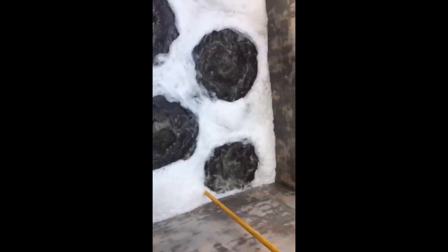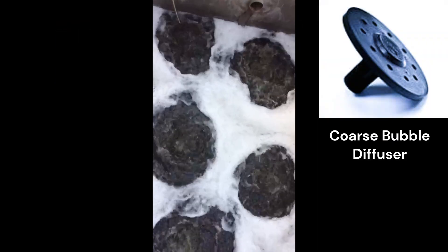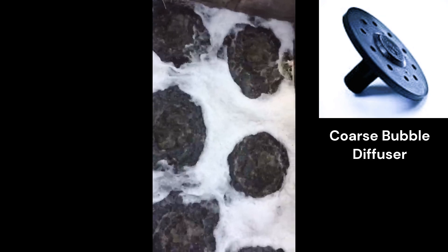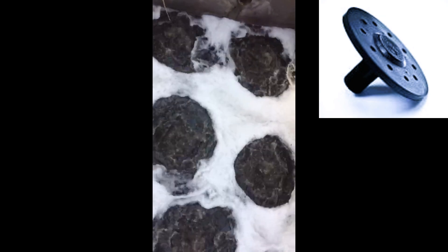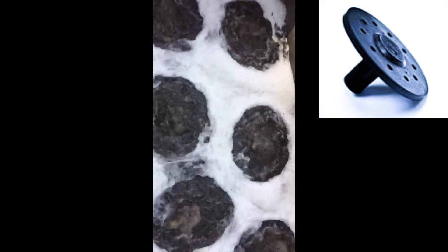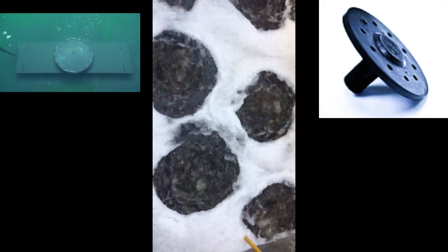The equalization tank doesn't just store wastewater — it also incorporates coarse bubble diffusers, which play a crucial role in the treatment process. Coarse bubble diffusers are specially designed devices that release large air bubbles into the equalization tank. These bubbles serve a dual purpose: agitating the wastewater and increasing the oxygen transfer efficiency.